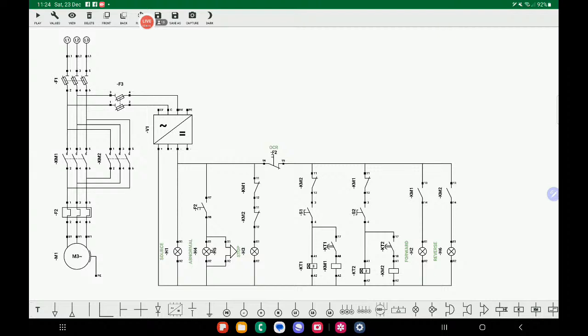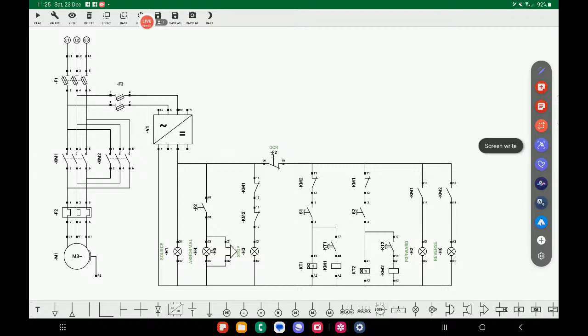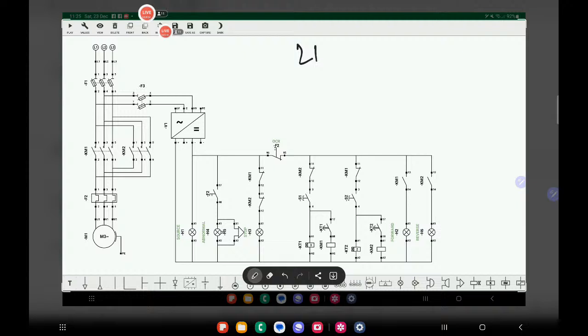I hope you will give a comment on what your preferred status is when it comes to fixing or troubleshooting certain machinery. Is it a live circuit or a dead circuit, and why did you choose that kind of condition? For me, I like to fix a certain trouble when it is a live circuit. In this way, I can put one of my probes into the closing loop and the other probe wherever I need, whether I am measuring AC or DC voltage, or even the resistance or the continuity of our system.